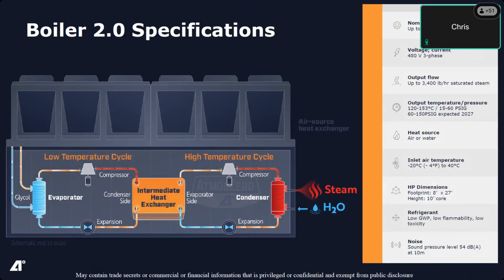So this is a schematic of what we have from inside the box, if you will. It's a cascaded heat pump technology, so you have basically two heat pumps in one. You have a low temperature cycle running off an A2L or an A1 refrigerant, and then a high temperature cycle running off an A1 refrigerant.